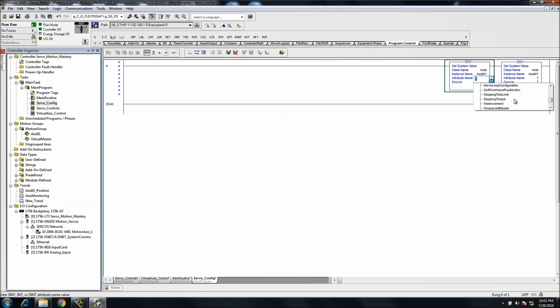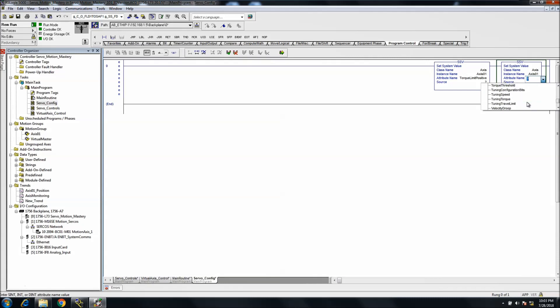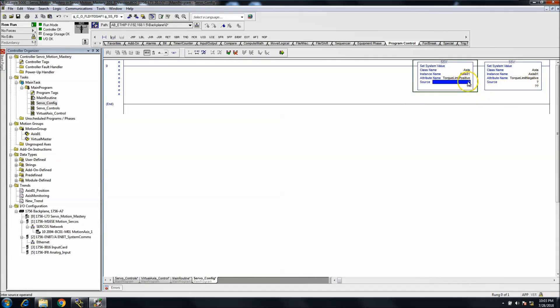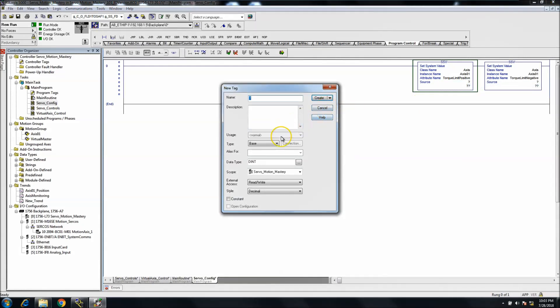What we're going to do first is set our torque limits - the positive limit and the negative limit. A lot of people ask how you get positive and negative. One thing you can do is make your tags: you can name them something like 'axis_01_positive_torque' for the positive, and then we'll do the same for the negative.